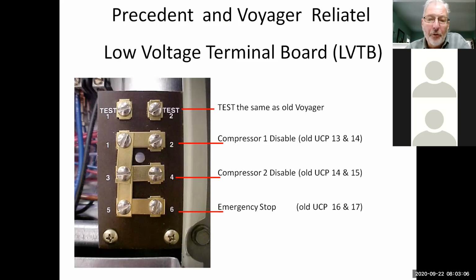Now, the other thing you can do is you can drive it through quicker. You can just take your jumper and go test 1, test 2 for a couple seconds and then take it off. It should go into test mode. And then if you want to drive it to the next step, hit it again. You know, test 1, test 2 for a couple seconds. Take your jumper off and it should drive it through. So you can force it through a little quicker by doing that.